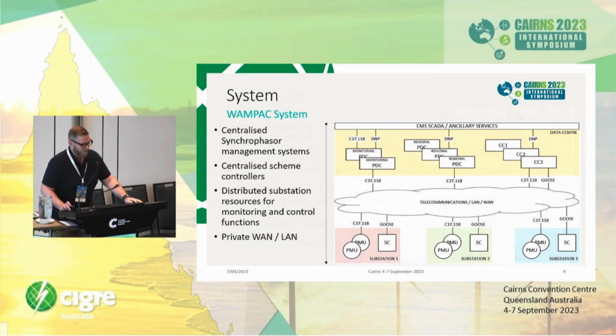But after our first trial, we went through the process of another project of getting our wide area monitoring protection control system up and running. The big part of that was that all the control we centralised. I won't go over too much for fear of spoiling what I'm about to talk about in about 2 hours. For example, at our reference node, we have 2 phase measurement units providing 2 voltage sources for redundancy. That information goes back to centralised phasor data concentrators, and at our generator buses, similarly, we have a phasor measurement unit providing the information back to the regional phasor data concentrators. Those data concentrators pass the information to central controllers. They perform the logic, and once the islanding conditions are met, the trips are sent to the necessary generator.